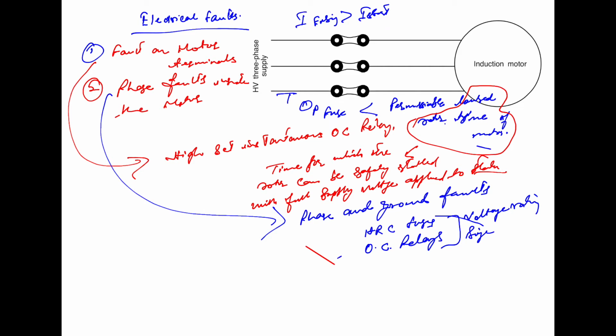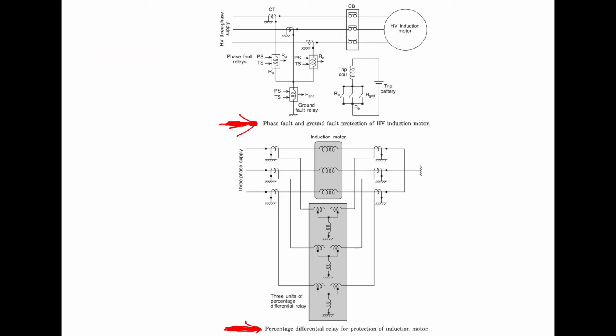Now, big motors with very high voltage, or high voltage motors, will need to be provided with overcurrent protection for increased accuracy. So if the voltage of the motor is high, then overcurrent protection is used for that purpose. The figure here shows the phase and the ground fault protection of the high voltage induction motor. As you have seen, we will have the phase fault relay and the ground fault relay. This is the overcurrent protection used for that purpose.